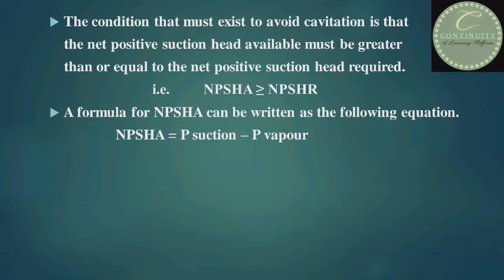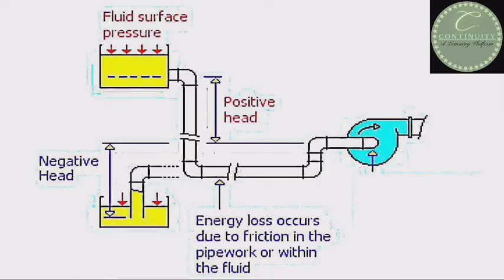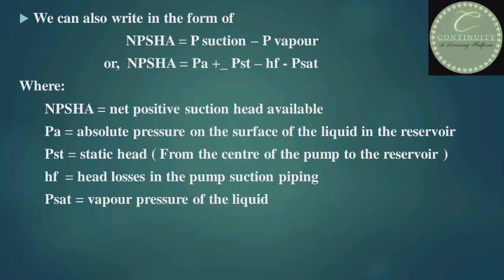The formula for NPSHA can be written as: net positive suction head available equals the difference between the pressure at the suction and the vapor pressure of the liquid being pumped. Liquid may come from storage situated above the pump or from storage situated below the pump. If liquid comes from storage above the pump, pressure at suction is measured as a positive head. If from storage below, it is measured as a negative head.